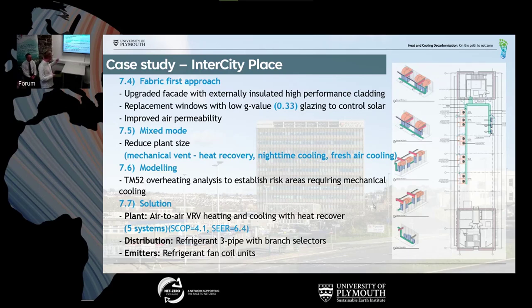Another important feature is the branch selector boxes. This essentially switches between the high pressure gas and high pressure liquid, so you can have heating or cooling in a room. That's all that does. It's heat recovery because say a room is in heating, it's providing that heat energy, but you're taking heat out of something else that then needs cooling, and vice versa. So it's quite interesting.